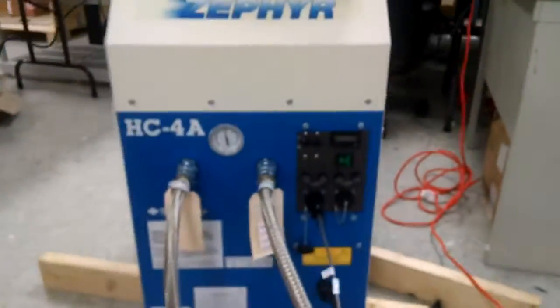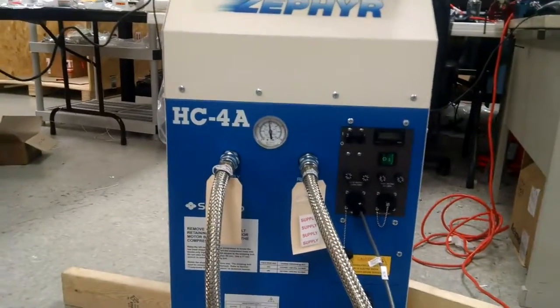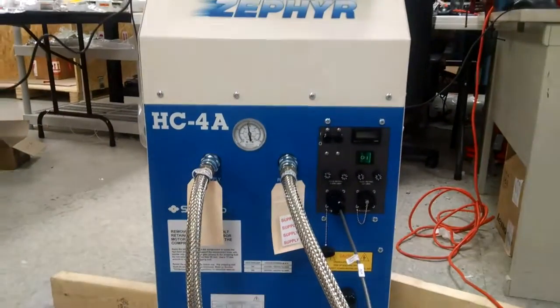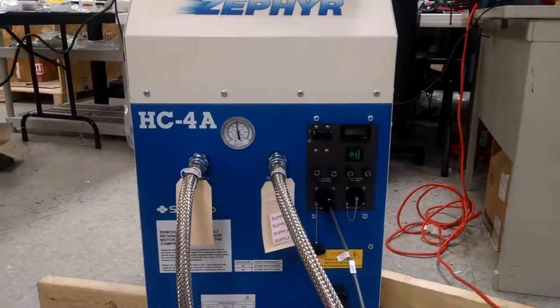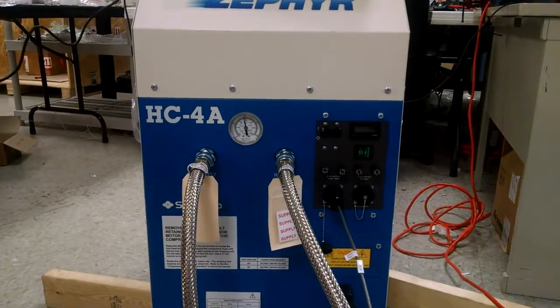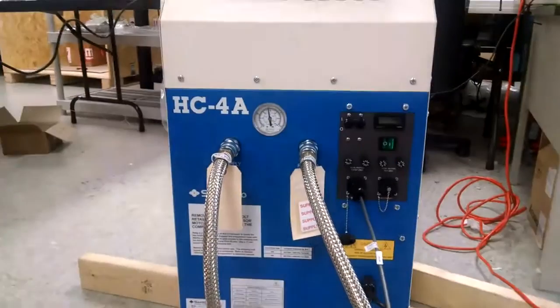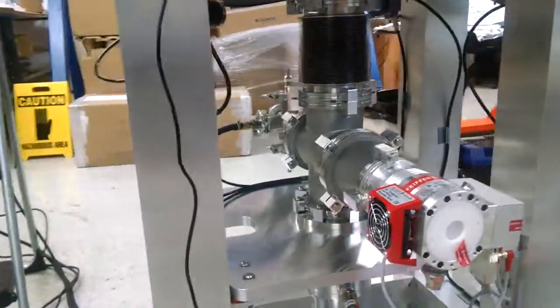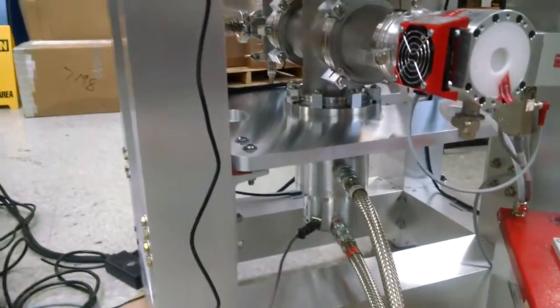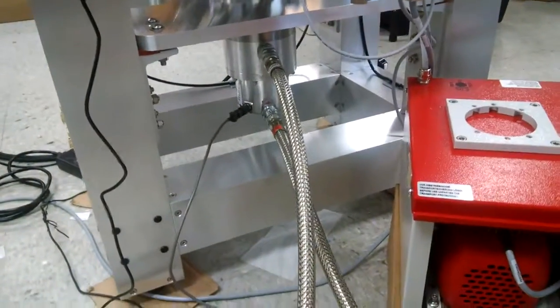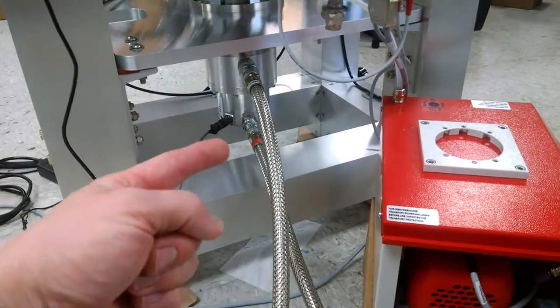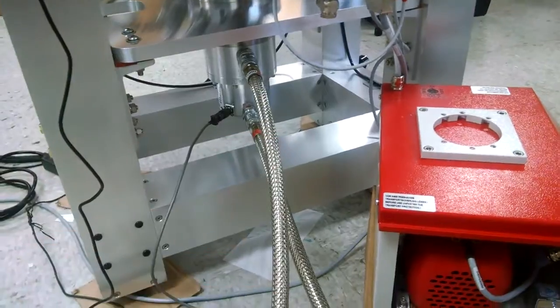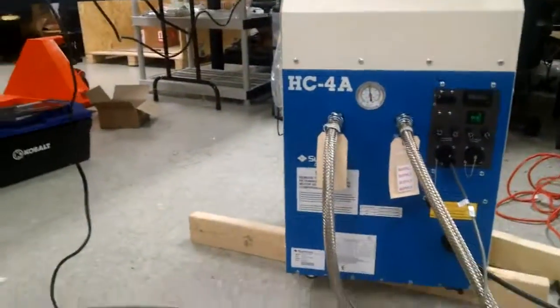So there it is, closed cycle refrigeration. So this system uses an air-cooled helium compressor. They have different models, and it just matches the particular cryo head that we picked here. So we have liquid helium going in the supply, gaseous helium going back to the compressor.